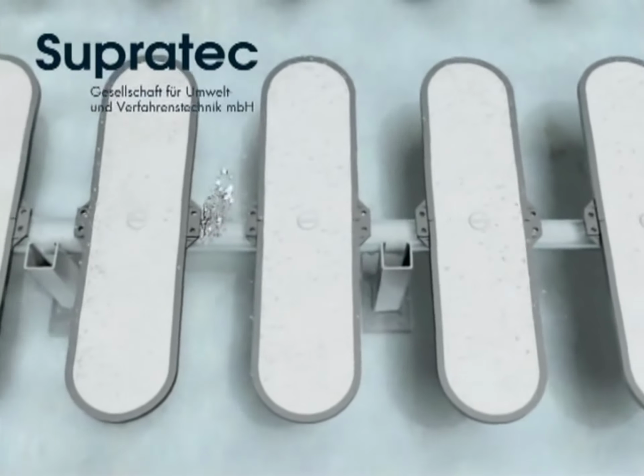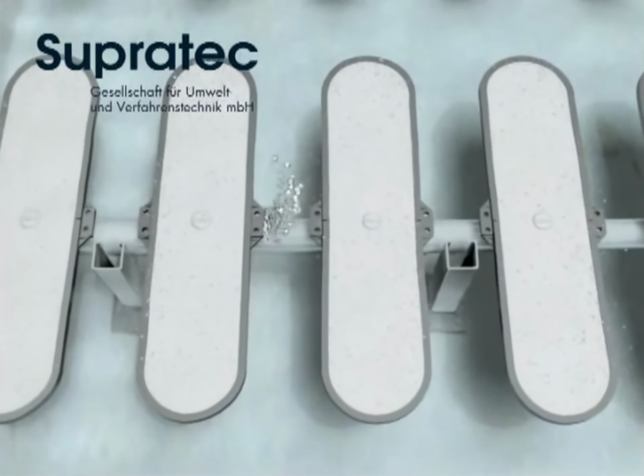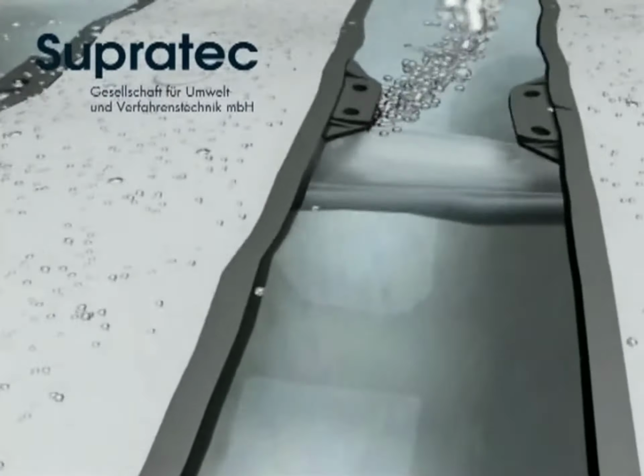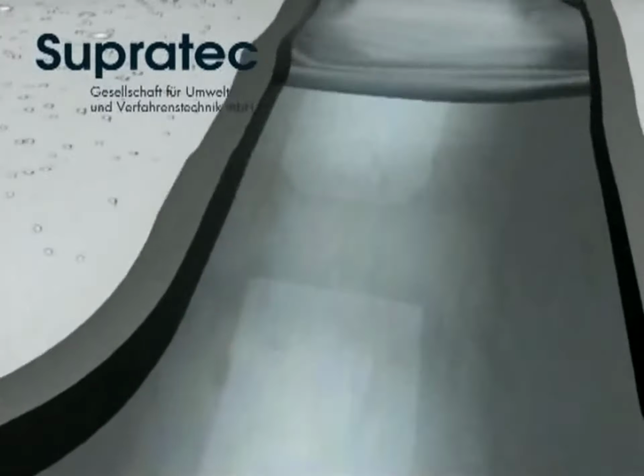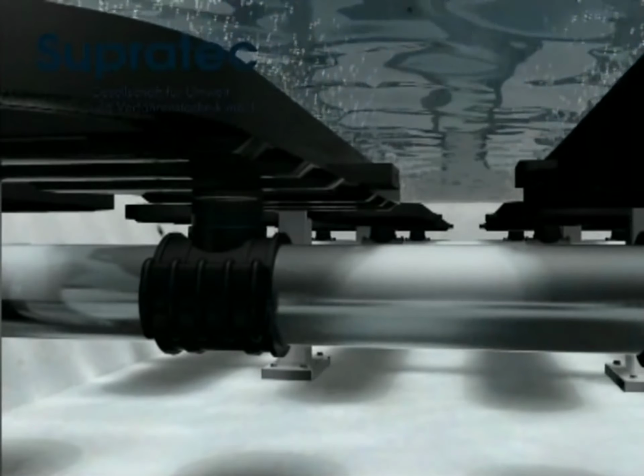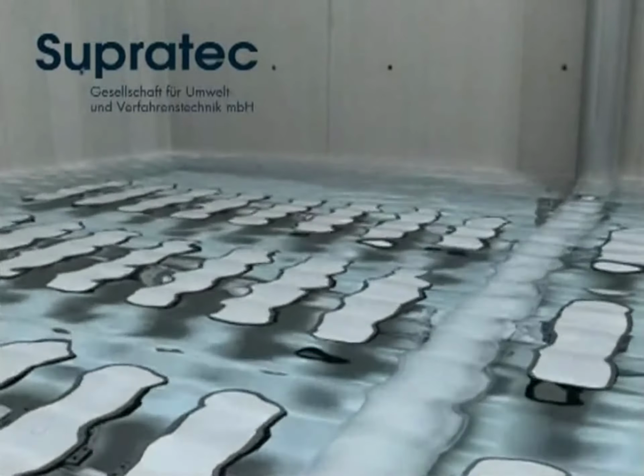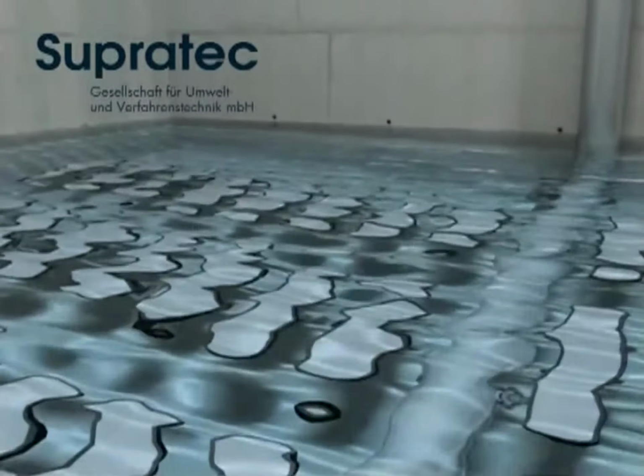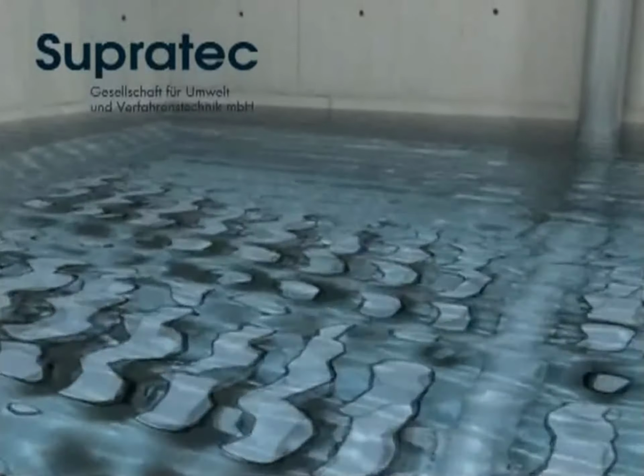Each individual aerator and each individual connecting point must be carefully examined. Only the trained eye will be able to detect all leaks. Every leak must be rectified. Defective or damaged parts must be replaced. The basin can be filled with more drinking water once the overall installation has been checked.